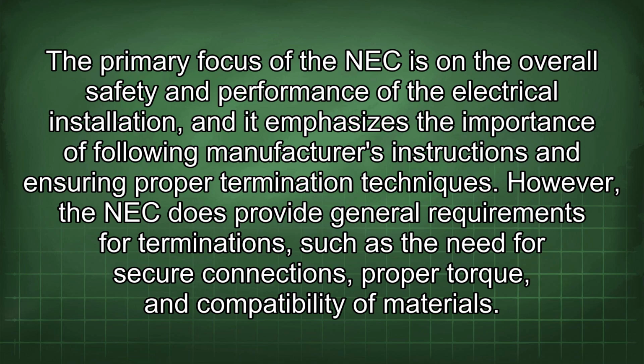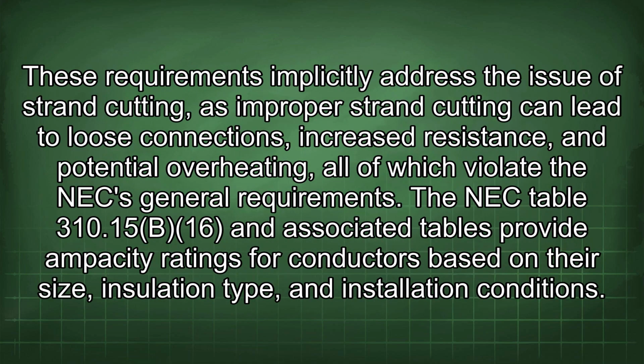However, the NEC does provide general requirements for terminations, such as the need for secure connections, proper torque, and compatibility of materials. These requirements implicitly address the issue of strand cutting, as improper strand cutting can lead to loose connections, increased resistance, and potential overheating, all of which violate the NEC general requirements.